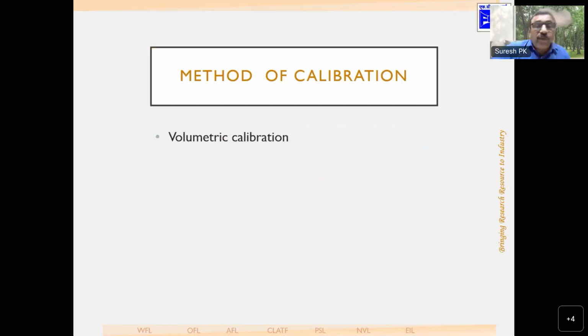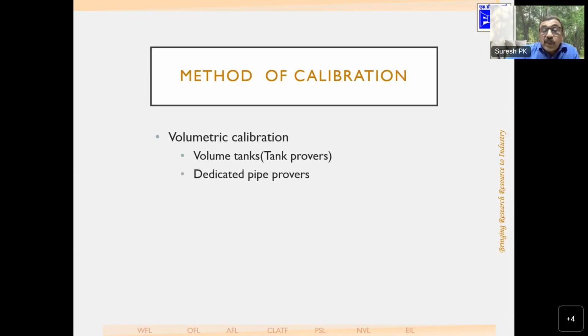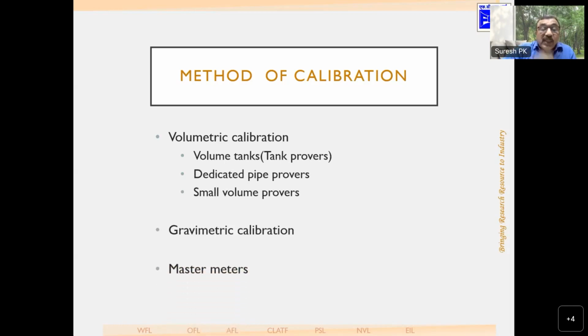So the fluid flow meter calibration can be based on volumetric calibration. It can be based on volume tanks, tank provers, dedicated pipe provers, or small volume provers. Then you have a method called gravimetric calibration, which is supposed to be the most accurate method. Then you have master meter methods. These are basically three kinds of methods which are used for the calibration of flow meters.